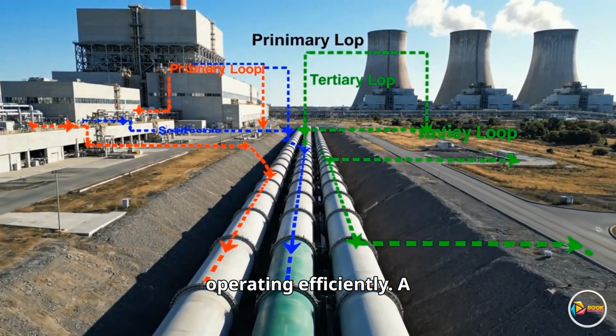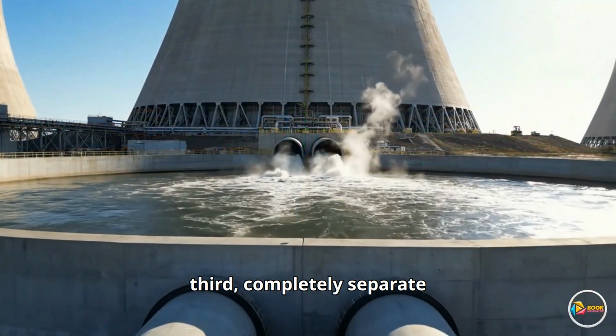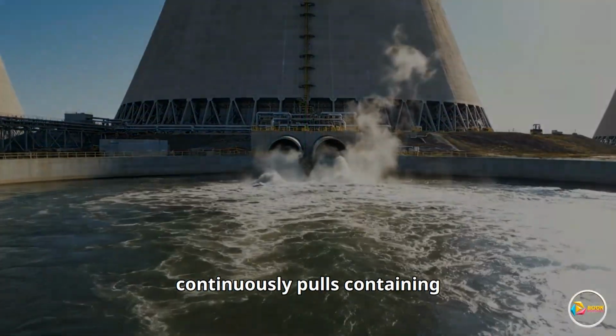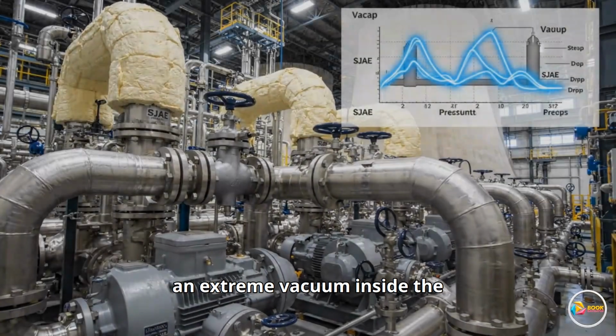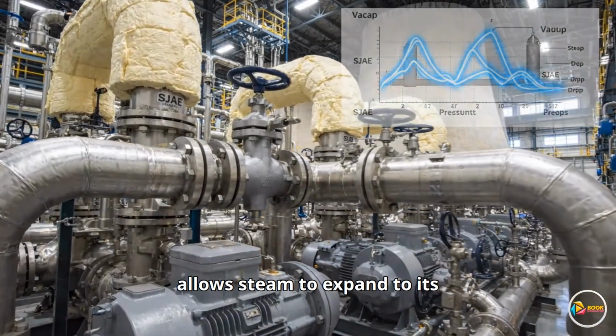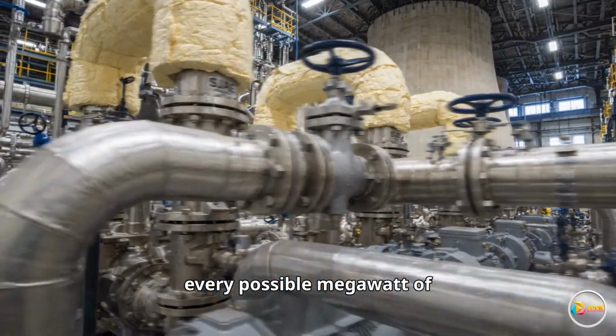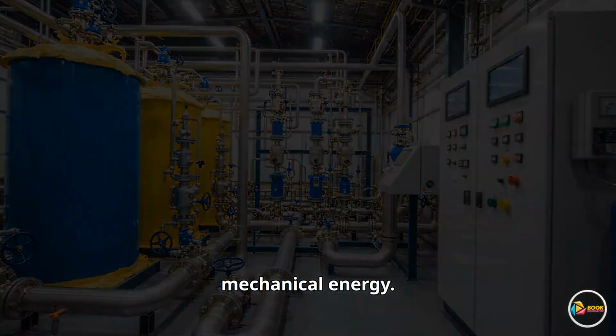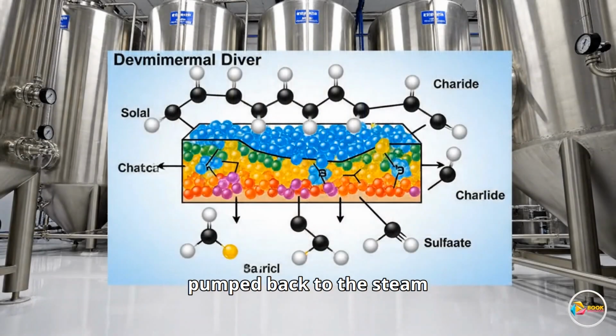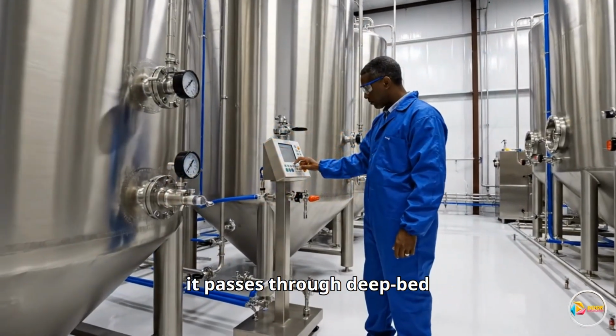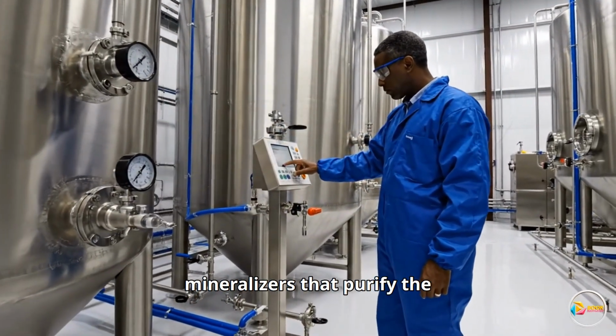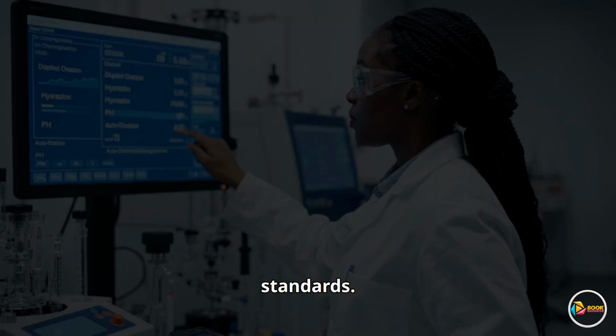To keep the steam cycle operating efficiently, a third, completely separate water circuit continuously pulls heat away. Maintaining an extreme vacuum inside the condenser allows steam to expand to its physical limit, extracting every possible megawatt of mechanical energy. Before the condensed water is pumped back to the steam generators, it passes through deep bed demineralizers that purify the water to parts per billion standards.